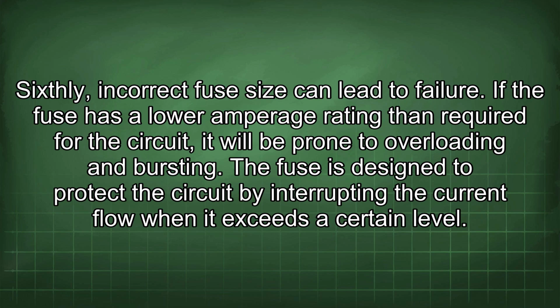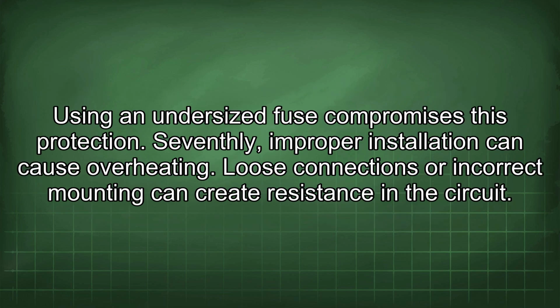Sixthly, incorrect fuse size can lead to failure. If the fuse has a lower amperage rating than required for the circuit, it will be prone to overloading and bursting. The fuse is designed to protect the circuit by interrupting the current flow when it exceeds a certain level. Using an undersized fuse compromises this protection.